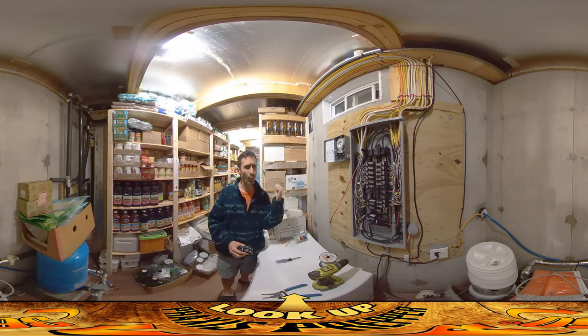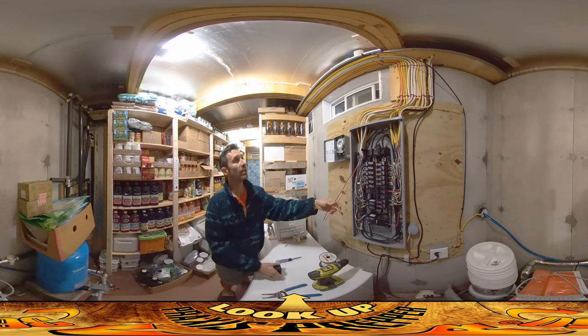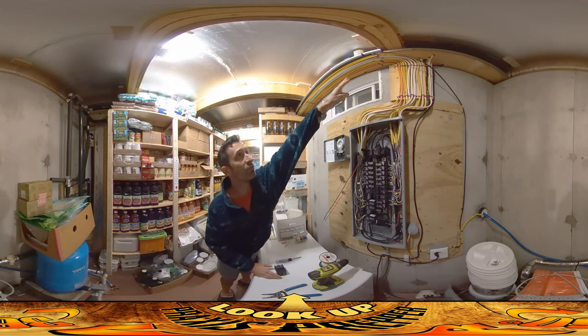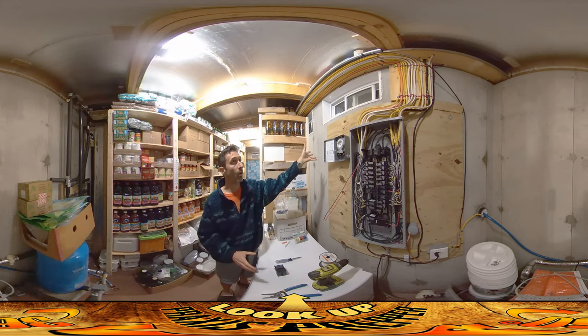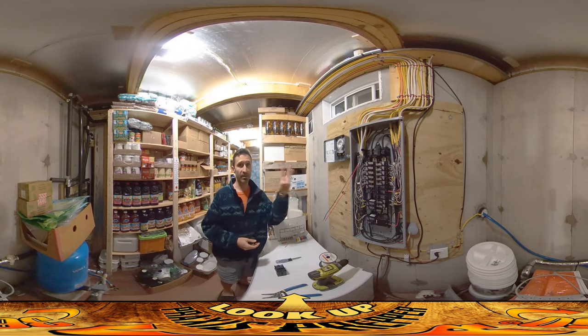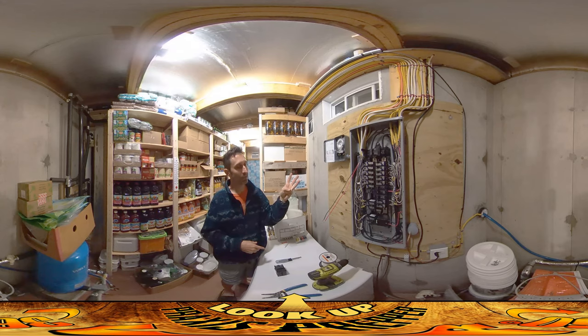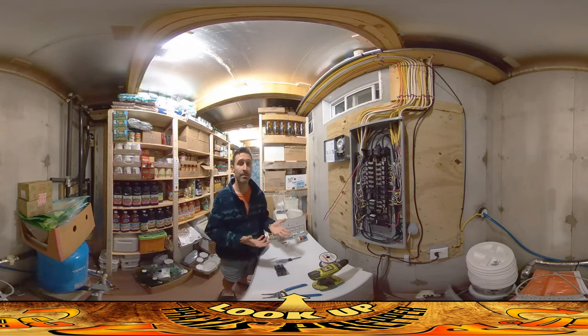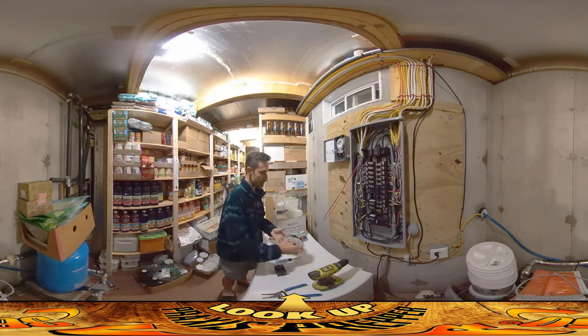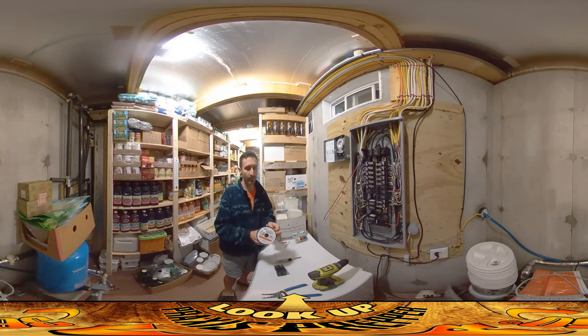It uses 220V which means it uses a dual-pole breaker. I just pulled this one out — these are the wires running to it through this orange Romex wire right here, I'm gonna call it the orange wire. It's called 10/3 Romex. The 3 means it has three leads plus a ground, which is actually four — they just make it confusing. It has three power leads running through it and the 10 refers to the gauge of the wire. 10 is a heavier gauge than 12 or 14 — the smaller the number, the thicker the wire. Just trying to make it confusing, I'm sure there's a technical reason for it.